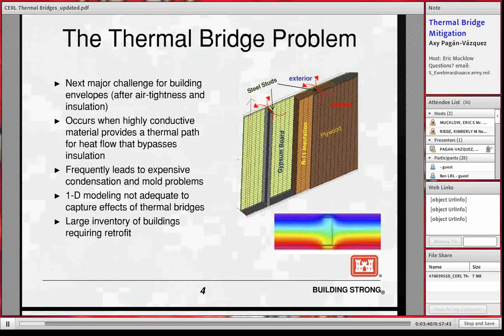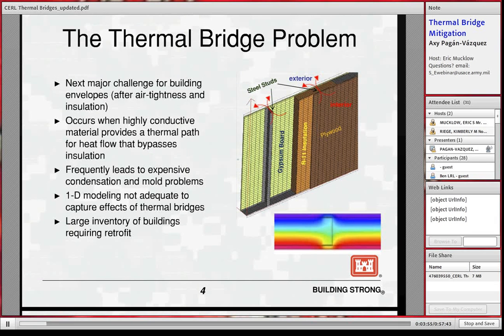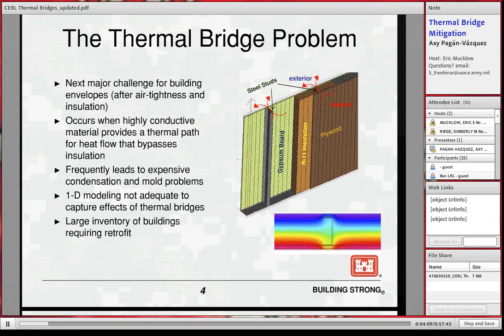After dealing with air tightness and insulation, the next issue regarding an optimal building envelope is thermal bridges. This usually occurs when heat flow bypasses the insulation layer of the building envelope system. This could lead to condensation and mold problems because of localized temperature differences. Regarding analysis, 1D modeling — the concept of unidirectional thermal resistance layers — is not enough to capture these thermal bridge effects.